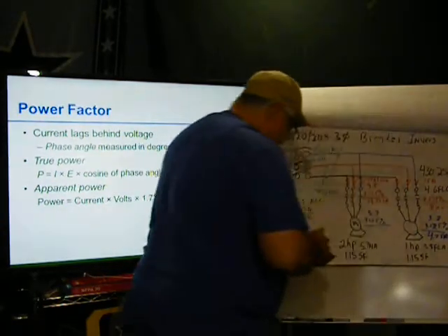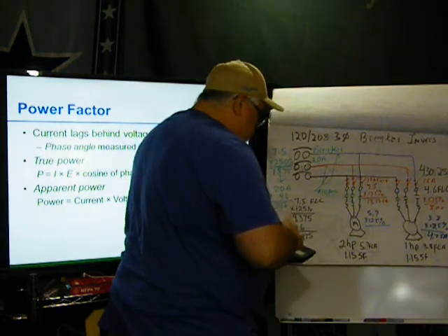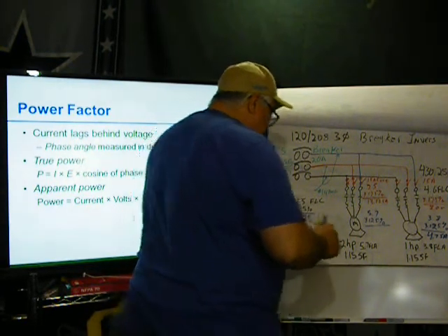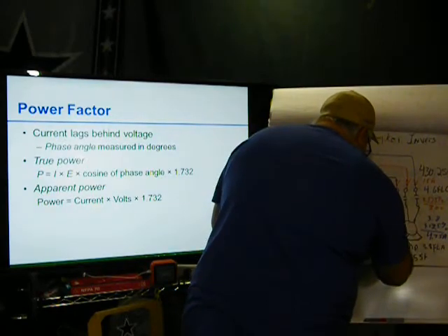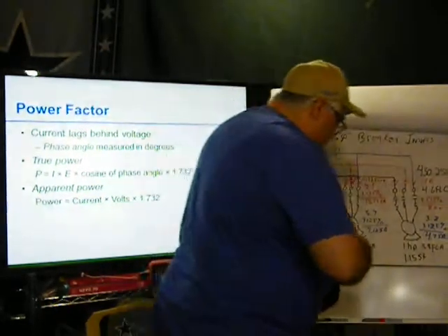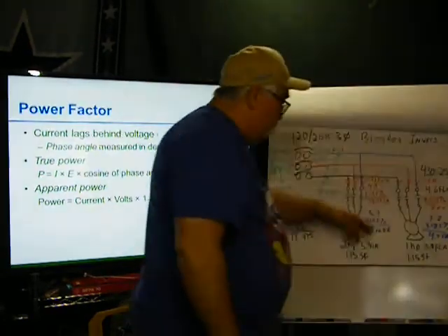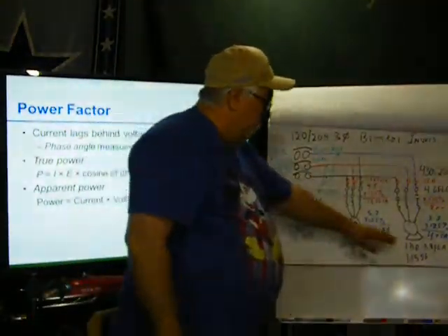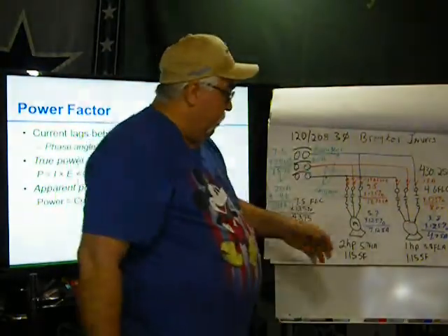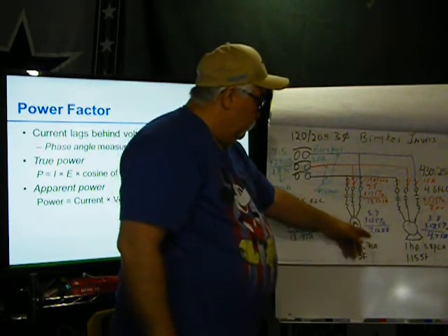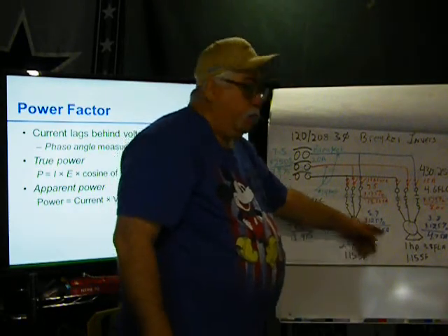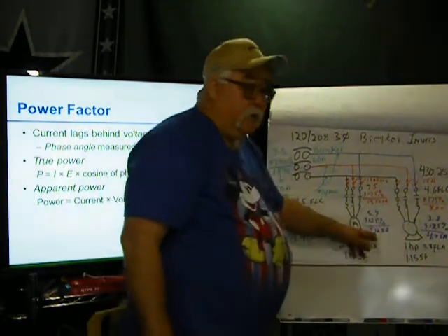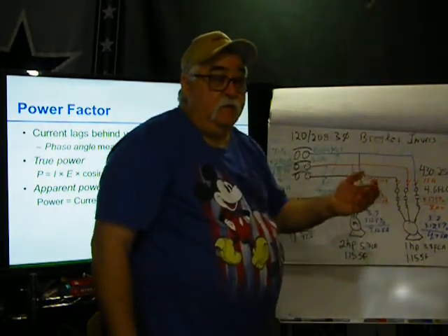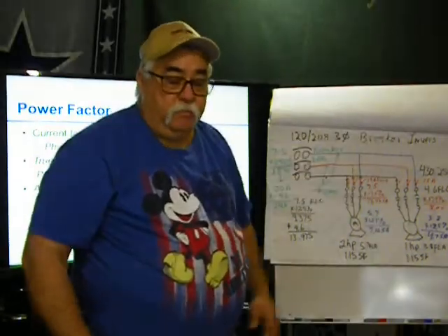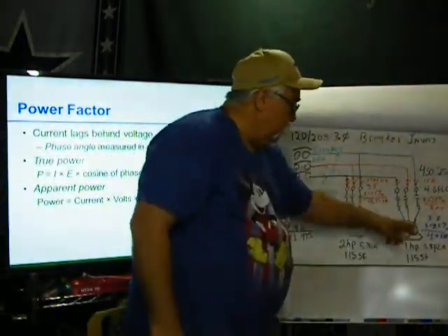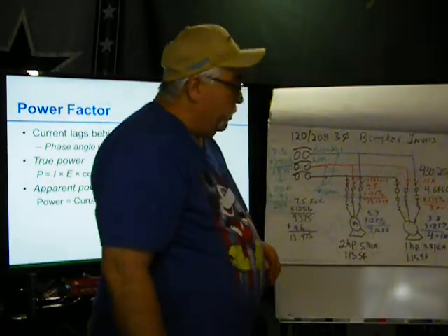.75 amps. .125 amps. Okay, on the overloads, don't round up, don't round down, because they come in fractions. So they always have, like, let's say it goes from 6.9 to 7.14. So now we know where we're at, and then it goes from 7.5 to 7.83. So they come in fractions. So when you get the overloads, always leave whatever pops up in the calculator. Always leave what pops up in the calculator.